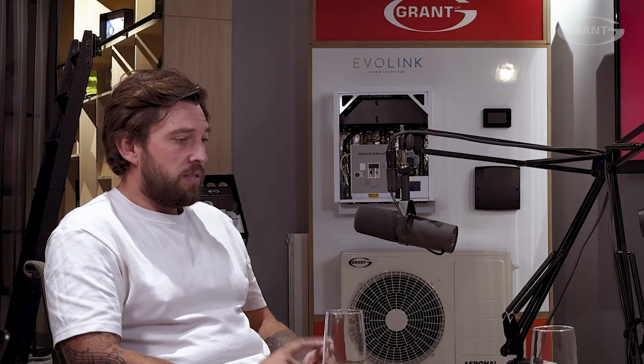Yeah. So design again, your heat loss, sizing correctly, and then commissioning right. If you get them right, you're going to have a good system, no matter what heat pump you've got. So a heat pump control, if it's set correctly, can increase the efficiency of a system, but if it's set incorrectly, it can have a negative effect on performance as well. Yeah, 100%. Apart from poor installation, if you've got two installations that have been installed right, but the controller's been set up differently, you'd see a big swing in how they perform. Whether you're overshooting floor temperatures, whether you're running it hotter than you need to. So yeah, control is the major part that squeezes out that extra efficiency for you.